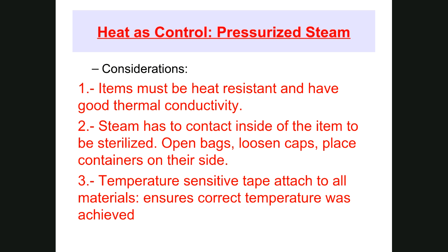So first thing is, can the item resist heat? If this is something that cannot conduct heat or cannot resist heat, and it's something you want to use again and again, you may not want to sterilize it in this manner. Keep in mind that the steam has to contact the item for it to be sterilized, which means if it's in a bag, you have to open the bags, loosen caps, place containers on their side. This also means that some things cannot be sterilized with an autoclave because the steam will not penetrate them.